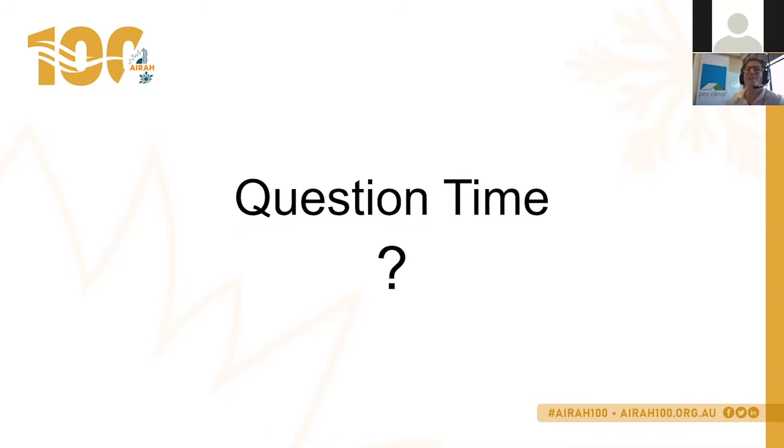Next, what are the key differences between DA07 and AIRAH 160? The key difference is that in some points it's just referencing the air leakage standard in the intermediate method for internal conditions, saying that for a building code compliant building for air tightness requirements, so 10 permeability on the air leakage, you should assume the standard setting on air tightness and not an airtight building.